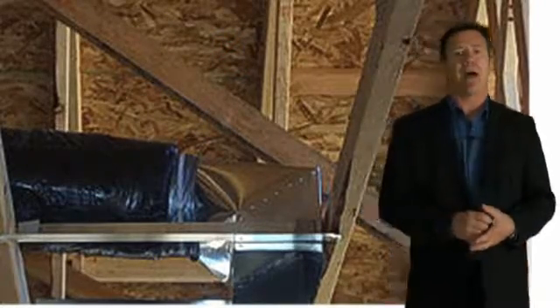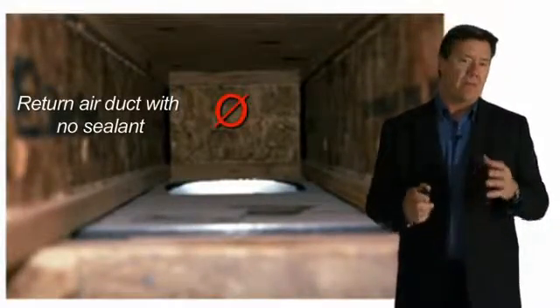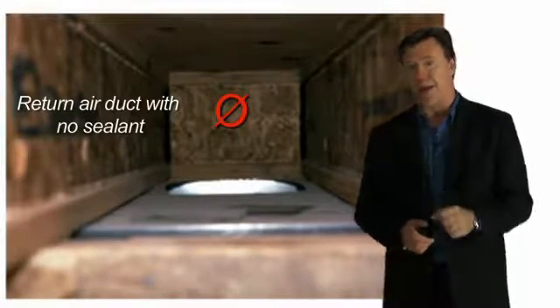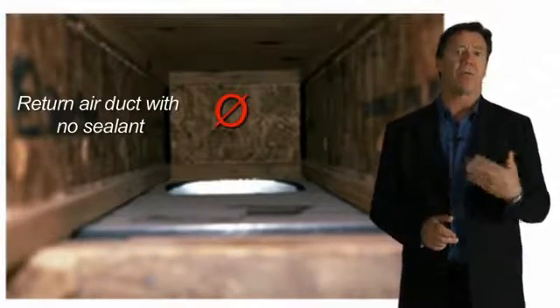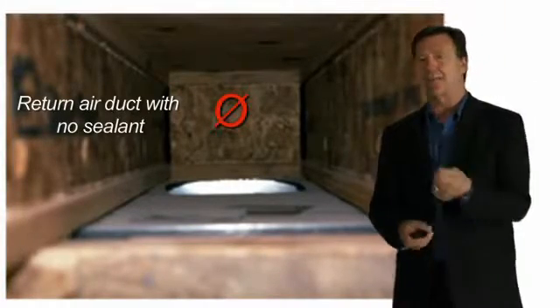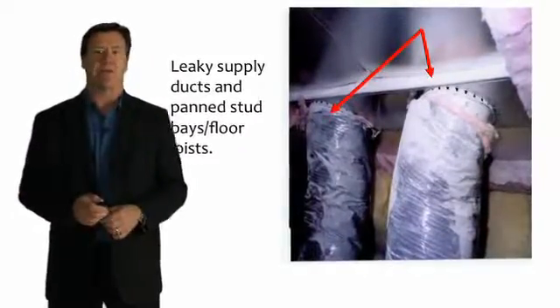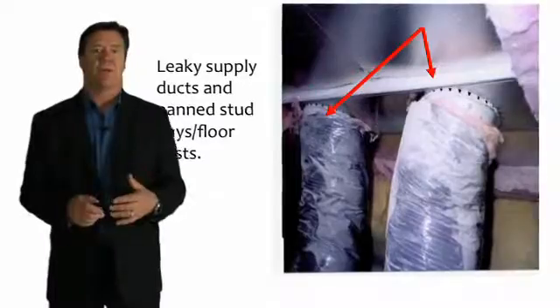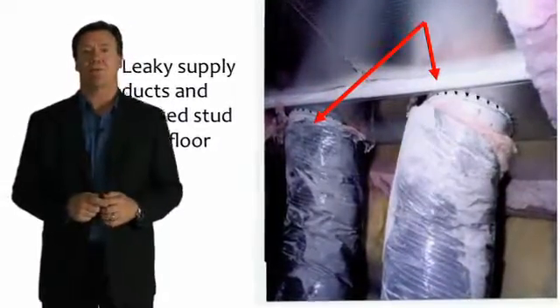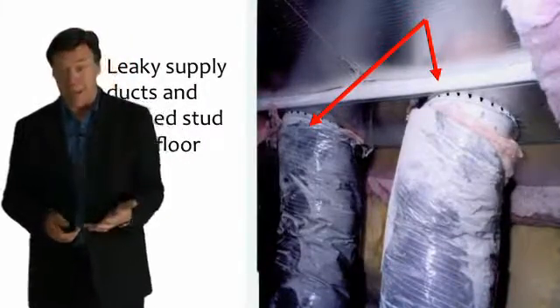In the lower picture, we see a return air duct that has no sealant. Any return air ducts using building cavities — while not a good practice — are allowed by code, but they must be sealed. Looking at these leaky ducts, the insulation is falling off them, and there's a transition between the plenum and the collar that mounts to the flex duct with visible holes all around it — that's going to leak and would not pass code. All duct work has to be sealed.